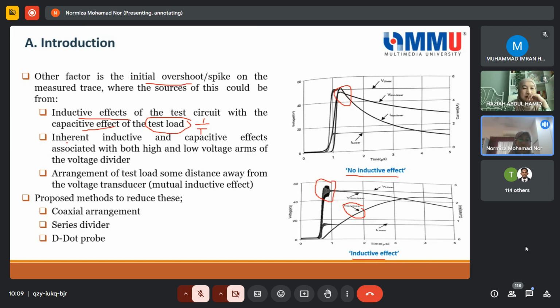And this one is also the same: inherent inductive, and another capacitive component other than from the test load is also from the voltage divider. So we will see the component of the voltage divider, especially the capacitive divider, like this, the high voltage arm and the low voltage arm. You have this capacitance at the high voltage arm as well as at the low voltage arm. So when combined again, the L and C give you the oscillation here.